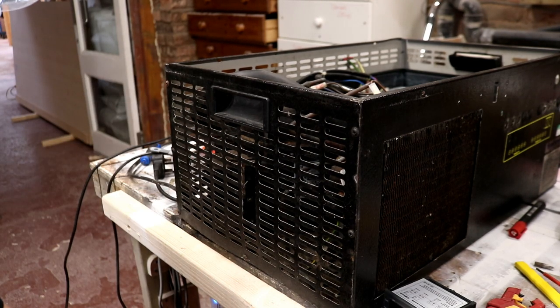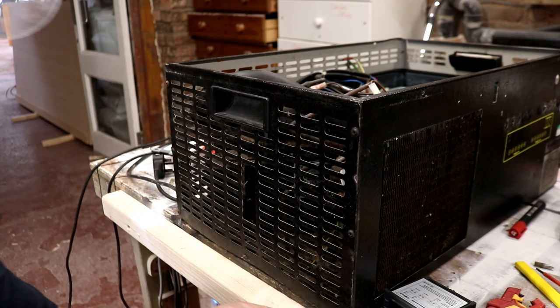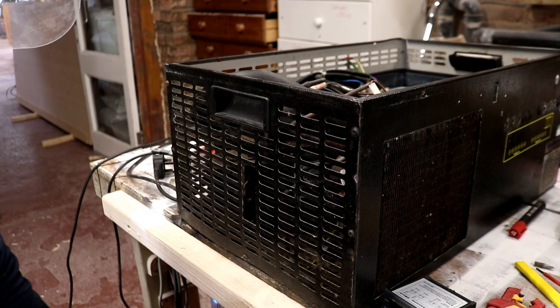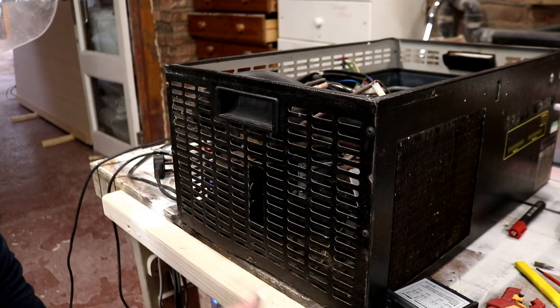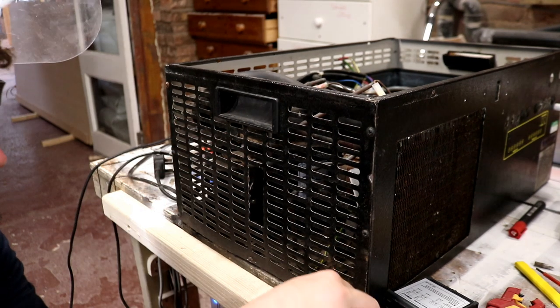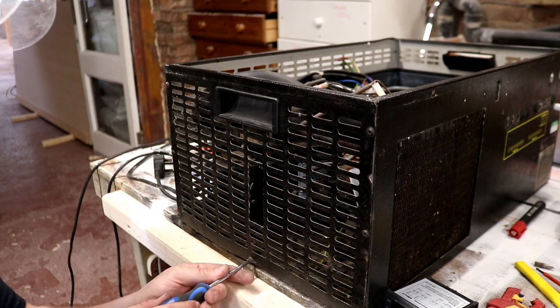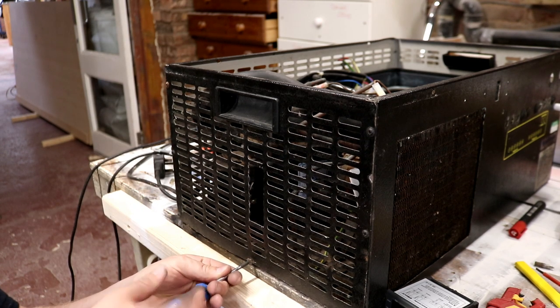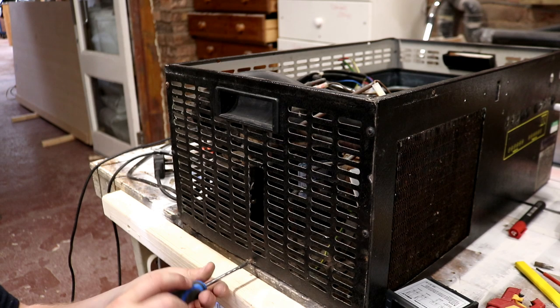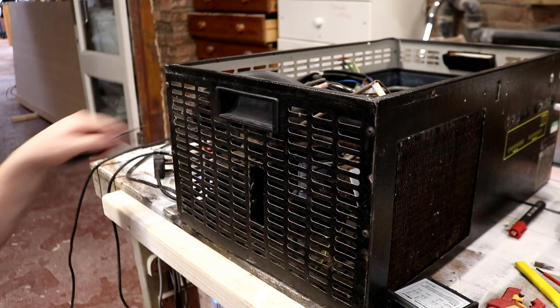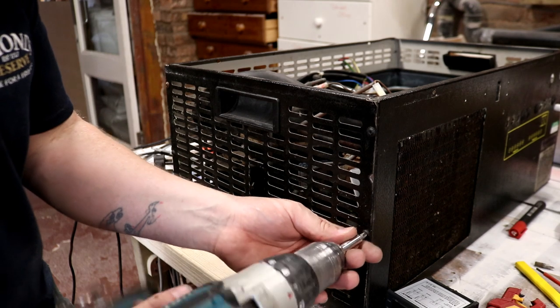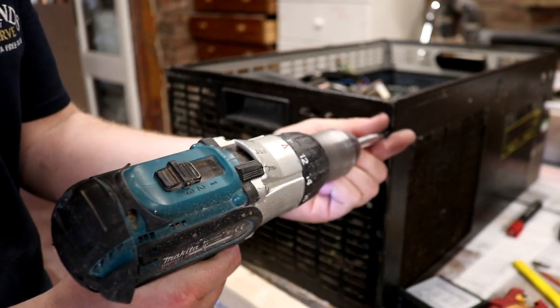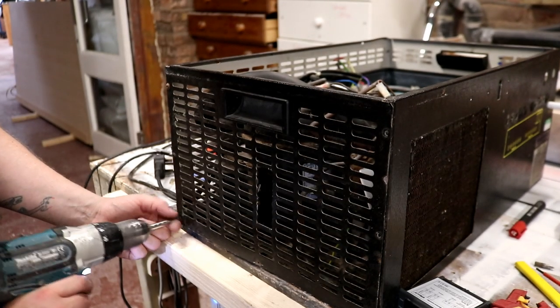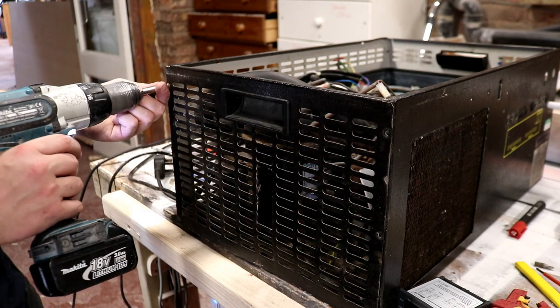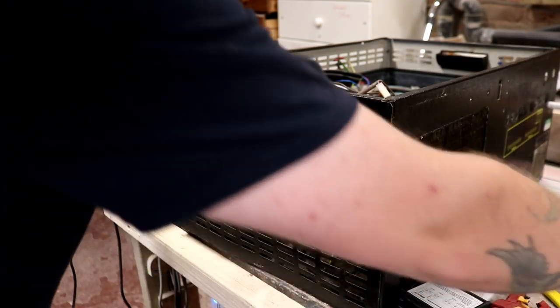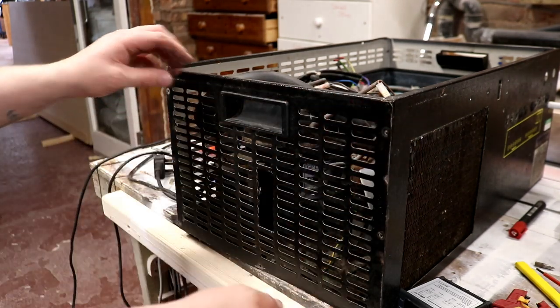I'm not concerned about hitting any of the pipework because I can see it all straight behind the unit, behind these perforations. So all I'm doing now is removing these 6 or 7 screws - might be quicker if I just use the cordless - and this will then allow me access to the electrics on the other side of the panel so we can wire in the STC.